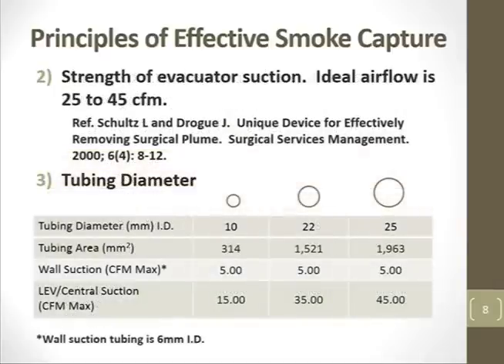The next thing that's important is, of course, the strength of the evacuator. The smoke evacuator is a turbine, usually located in a box, that powers the ability of the device, which is, of course, a passive thing. It has no power in and of itself, and brings the smoke away from the operative field. The stronger the smoke evacuator is, that is, the more airflow it can generate, the further will the column of smoke travel. Let me say that again. The more powerful the smoke evacuator in terms of the amount of airflow that it can produce, the further the column of smoke will travel toward the collection or capture device.